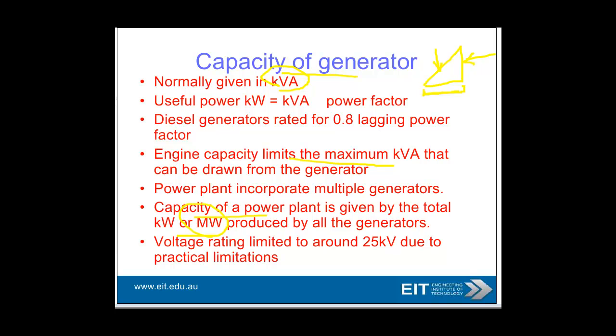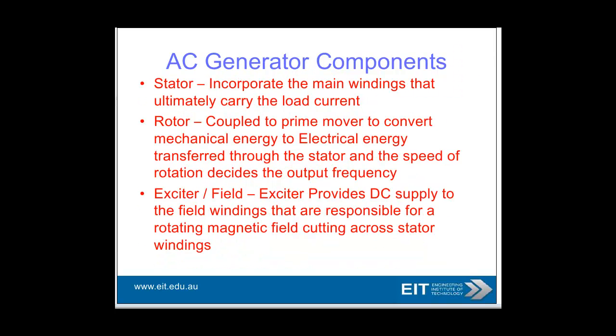So engine capacity limits the maximum kVA, and obviously capacity of power plant is the total megawatts that you produce. And voltage is typically 25 kilovolts due to the practical limitations of the windings and the structure. Other generator components are the stator, which is where the windings carry the load current, the rotor, which is a rotating bit, and that's connected to your diesel engine or prime mover, and that converts from mechanical to electrical energy.